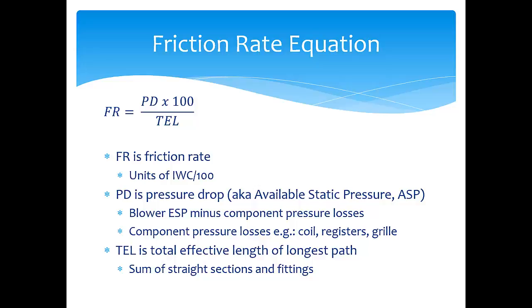The total effective length only applies to the longest path in the duct system. When we talk about effective lengths of fittings, for every duct contraction or turn — say a 90-degree turn — testing has been done to provide the length of straight duct that produces the same pressure drop. That's why we call it the effective length. Please keep in mind that the total effective length only applies to the longest path in the duct system.